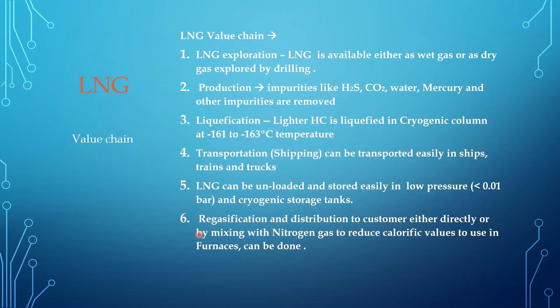The next step is regasification. Regasification is done in onshore facilities or in an FSRU — Floating Storage and Regasification Unit — itself, using a heat exchanger with either seawater or glycol solution as the heating media. After regasification, the gas is distributed to the customer directly, or mixed with nitrogen gas in the metering section to reduce the calorific value before being sent to furnaces.